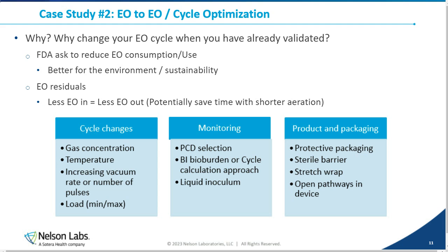But things to consider with this, so one is going to be the cycle changes themselves. We're going to be changing our gas concentration. We're potentially going to be increasing our temperature for increased reactivity of the gas. That increase in temperature can affect the product as well as its packaging system. We're potentially going to be increasing the vacuum. So maybe we're pulling more vacuums in a shorter period of time or pulling deeper vacuums. Also looking at the loads, our min and max loading, maybe optimizing that so that we don't have to sit in the chamber as long because we've improved how much is available. Also with that, maybe I shrink my load so I don't have to use as much gas, so I have more gas available for reactivity.